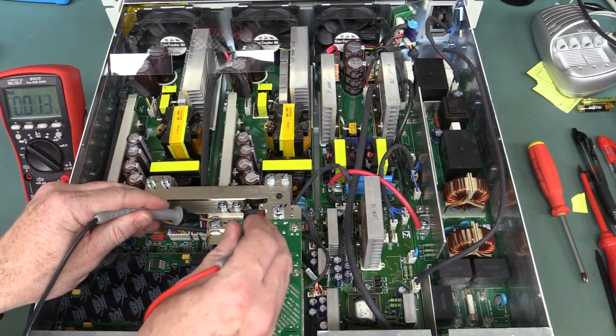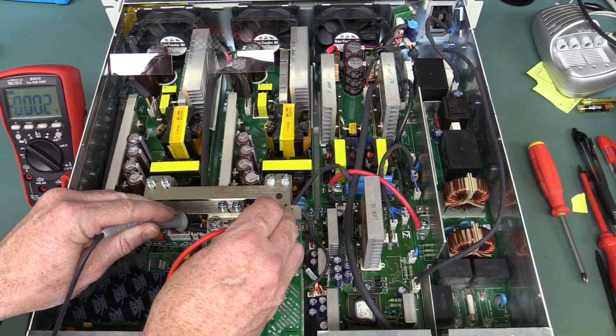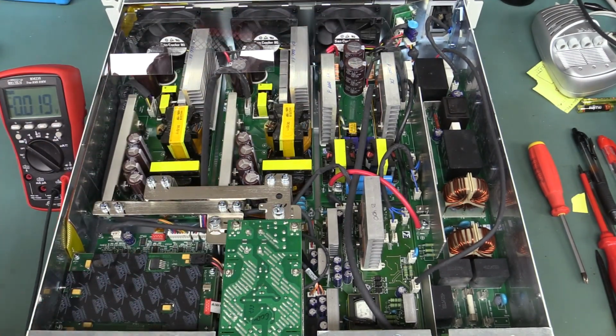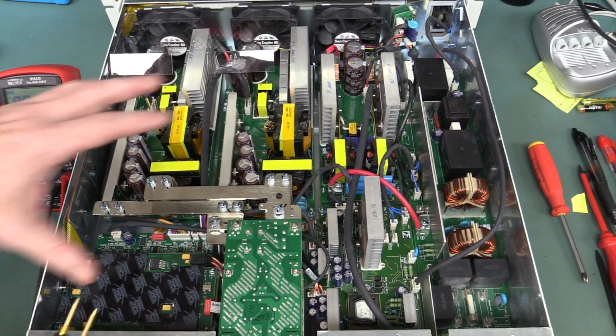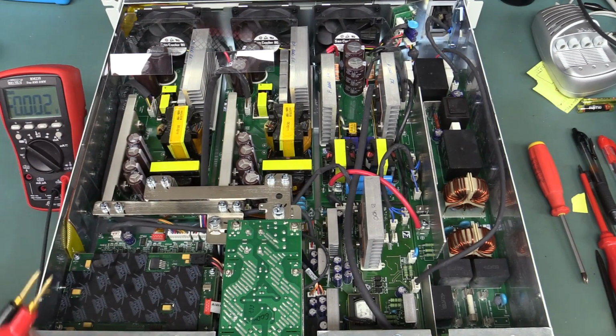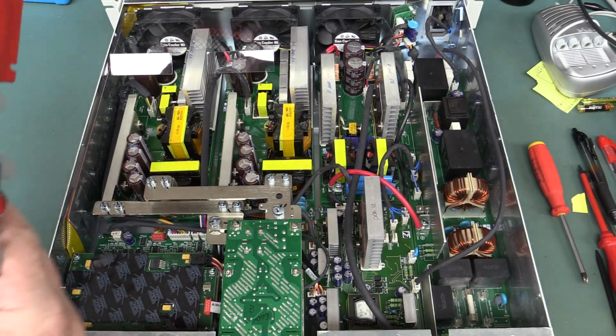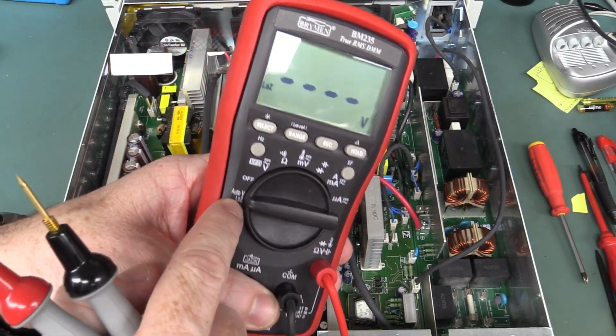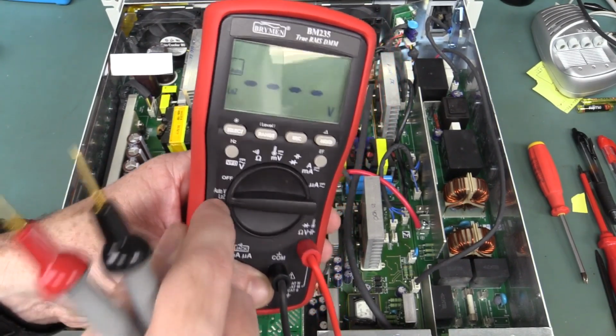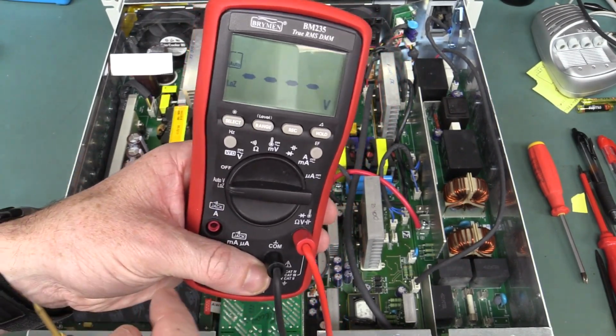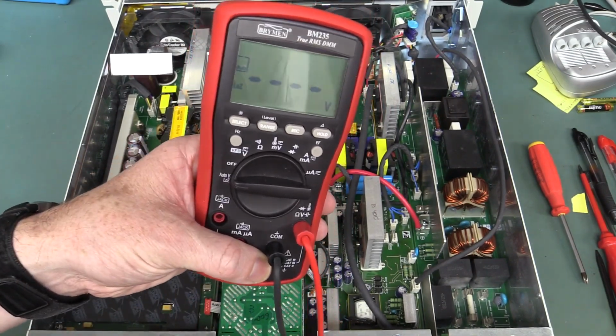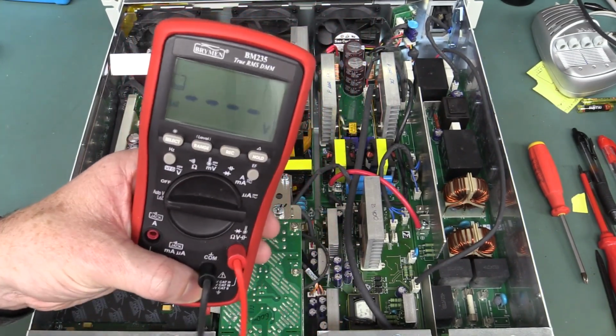So I'll get in here to this lovely looking bus bar, and I'll give that a probe, and yeah, bugger all, and then you can go probe the mains side, but yeah, it's all discharged. You just want to make sure this whole thing is discharged, both the secondary high voltage DC side and the primary side over here, all discharged before you go poking around in here. And just remember, if you want to discharge some things, if you've got a multimeter with one of those low Z modes, that'll do the business. It'll put a resistor in parallel with the cap, and it will discharge it, and it'll display the voltage as it discharges.